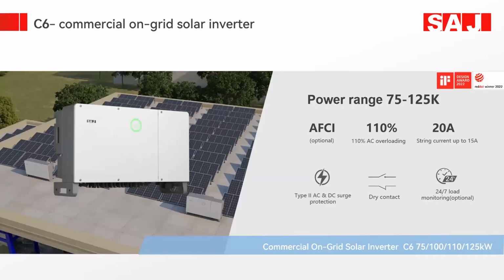Now we will talk about the C6 commercial on-grid solar inverters, which is the commercial inverter series installed in industrial sites. In the Pakistan market, we have installed almost 10 inverters of C6 125 kilowatt, and a few inverters are going to synchronize with the PV diesel hybrid controllers as per company requirements, genset systems. And we will also discuss the genset controller configuration in this commercial series on-grid inverters.